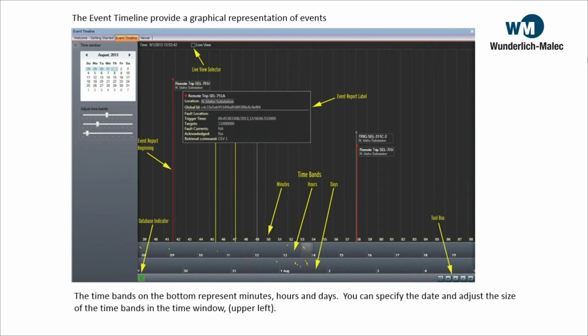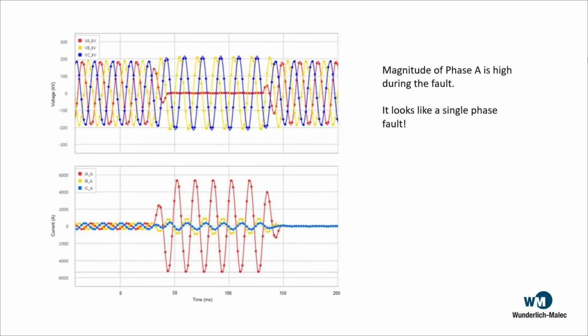With that quick interface, which is a very easy drill down, we can pull up the actual alternating current waveforms of that incoming feeder that tripped out. We've got a high magnitude current on phase A, and it looks like a single phase fault on our feeder coming into the plant.